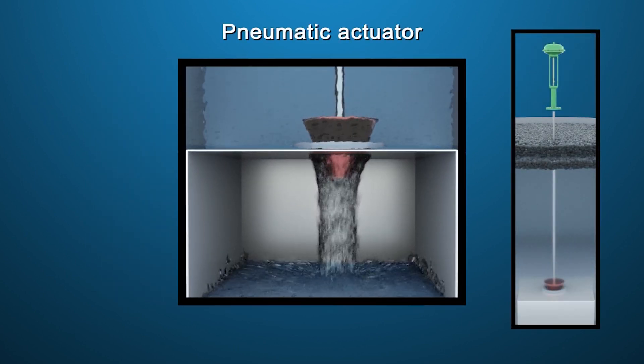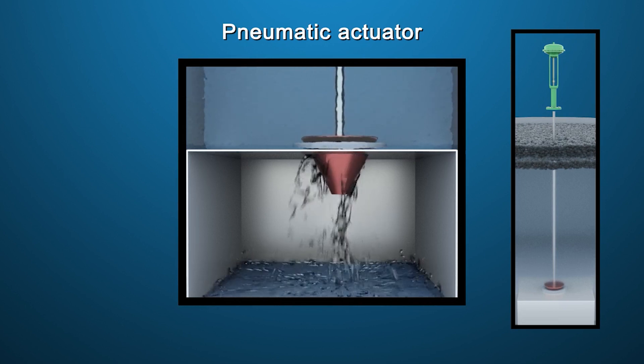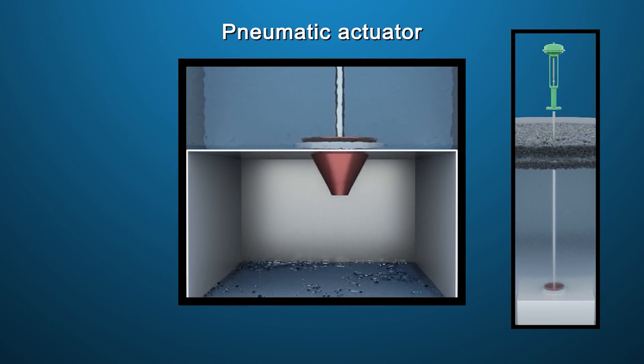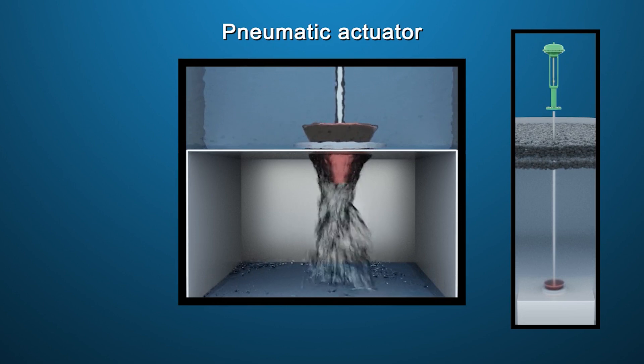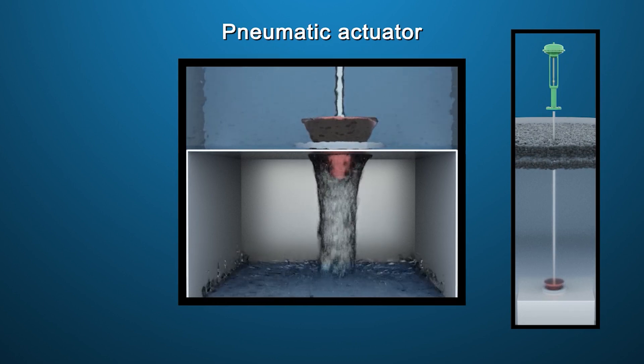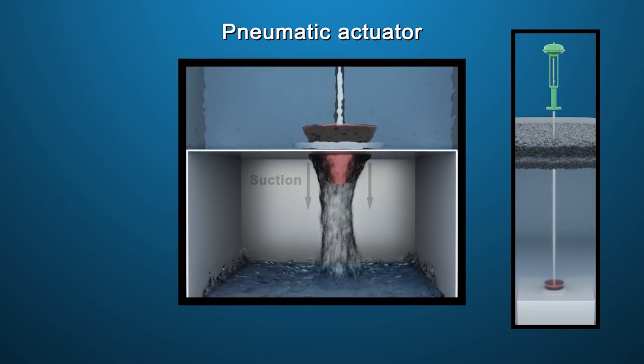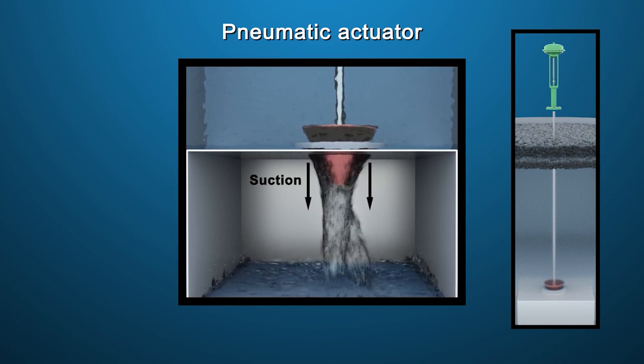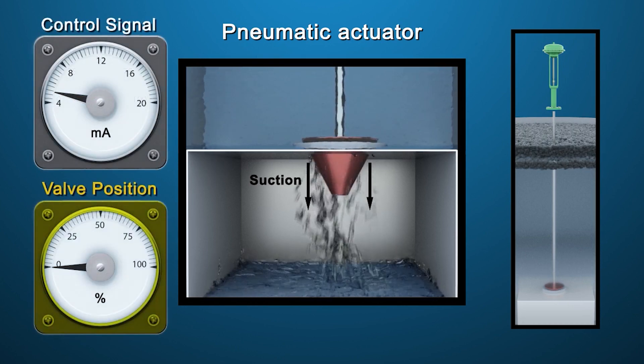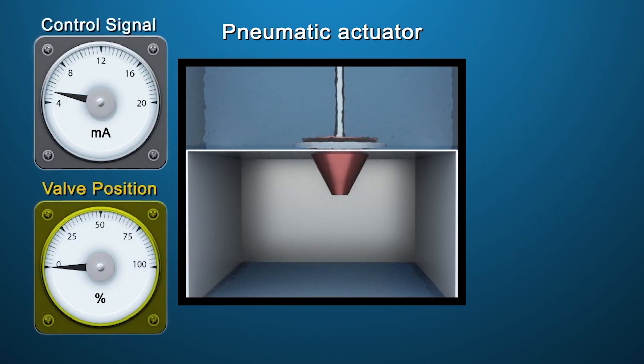Typically, dart valves are operated by pneumatic actuators. Maintaining pulp level requires small, stable set point changes. Flow exiting the dart valve creates suction, which pulls the valve closed. This is problematic for pneumatic actuators, which must overcome air compression and static friction before valve motion can occur.